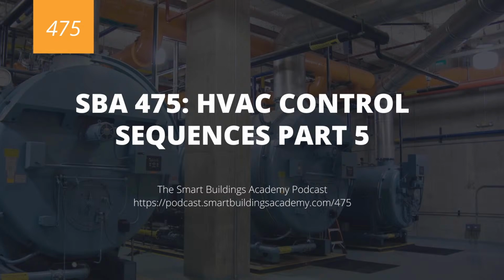First, we're going to start off with a single hot water boiler. And where can we start? Well, typically we're going to start by focusing on the three things we need to have control of. This is really important to understand because when you're troubleshooting boilers or programming boilers, if you don't have control of these three things, you're typically not going to have very precise control, and in some cases, you will not be able to get the system to run. Those three things are flow, fuel or power, and obviously control. So flow is critical. Without flow, we can really mess stuff up.